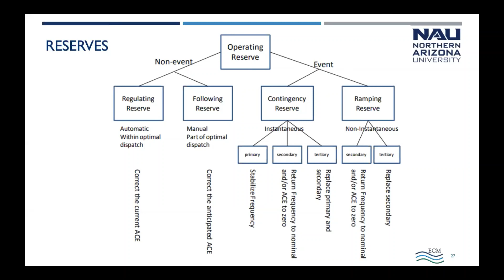The balancing area authorities use reserves to balance the system. When load and generation don't match, you need to use reserves to make them match. You have non-event actions, like regulating reserves and following reserves, and event reactions for when you aren't expecting a change. So you have reserves set aside specifically to anticipate things like the daily increase or decrease in load, and then event reserves for when you might lose a transmission element.